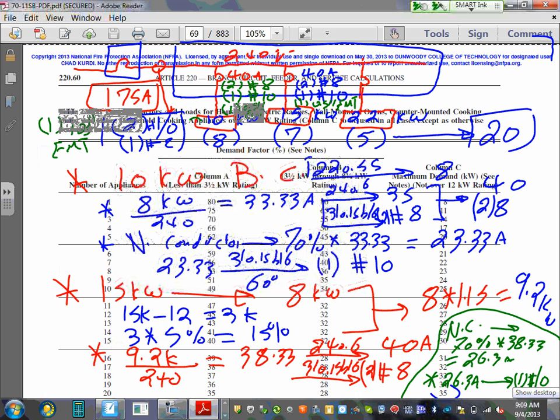No, there are two different sizes. You can't use this. Did you use math? Yeah, well, that's why I said 0.164 and then 0.216 times 2, and you get like 0.596 for a total diameter. You add them up and you came up with a different size? Well, 0.596, that's what I got. No, you have to use a 40% fill. Yeah, this is based on a 40% fill. 3 conductors.